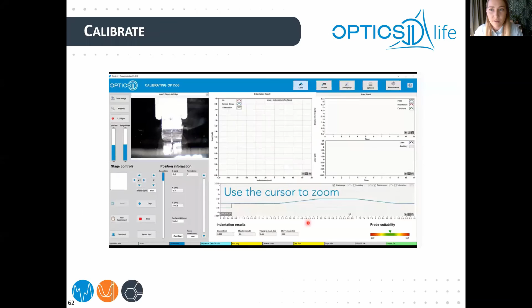Yes, so now what is the calibration factor? I just wanted to quickly explain. The movement of the tip takes place at the tip. That's where the actual indentation takes place. However, the fiber reads out the position of the cantilever here. Now that's not the same distance. The tip moves more than what the fiber sees. So this is called the geometrical factor correction, if we just take the ratio between these two distances.